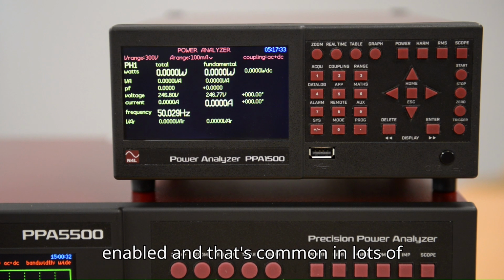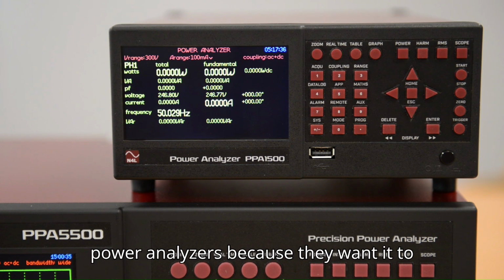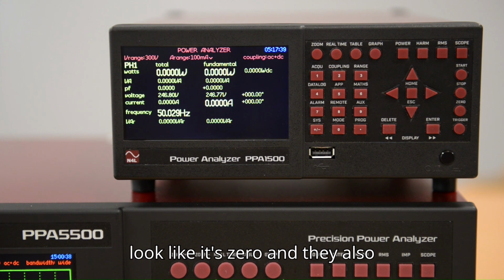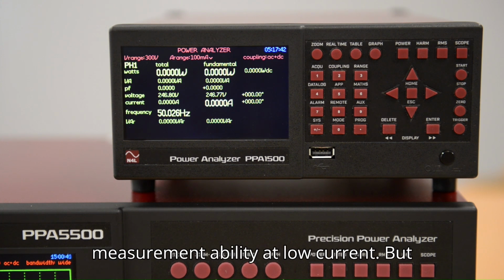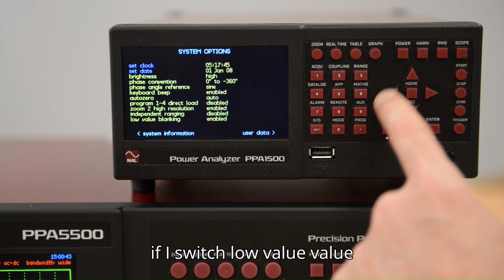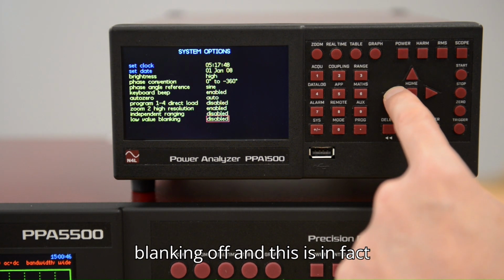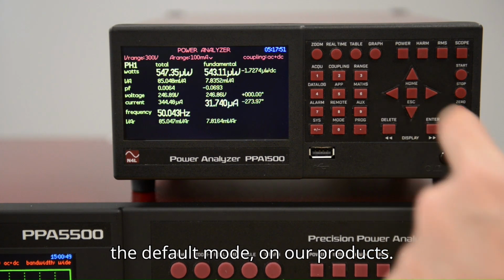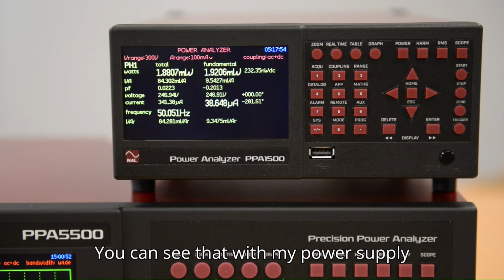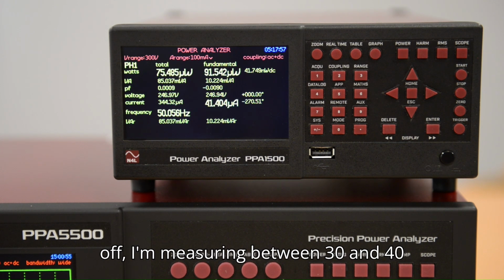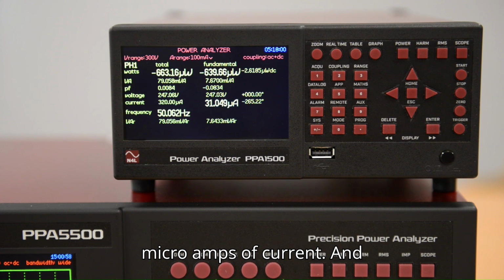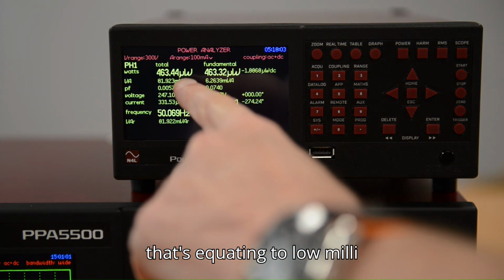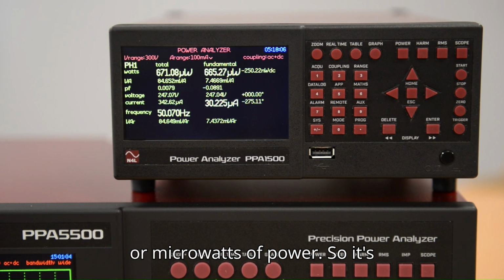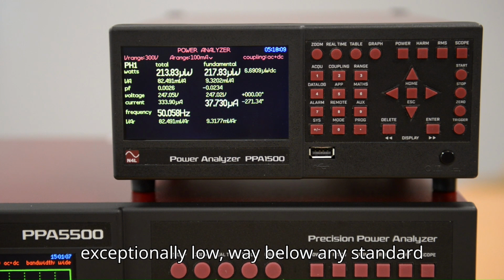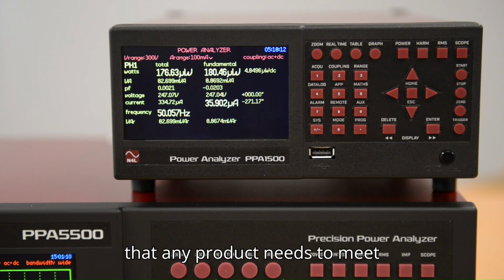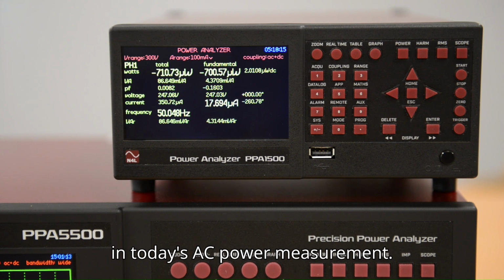That's common in lots of power analyzers because they want it to look like it's 0, and they also hide the absolute resolution or measurement ability at low current. But if I switch the low value blanking off, and this is in fact the default mode on our products, you can see that with my power supply off, I'm measuring between 30 and 40 microamps of current. And that's equating to low milli or microwatts of power. So it's exceptionally low, way below any standard that any product needs to meet in today's AC power measurement.